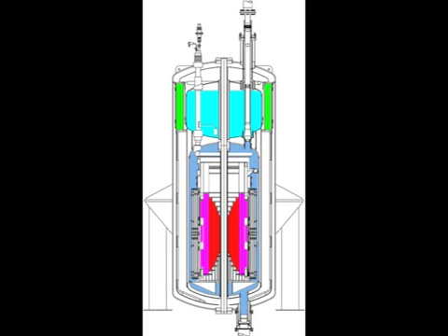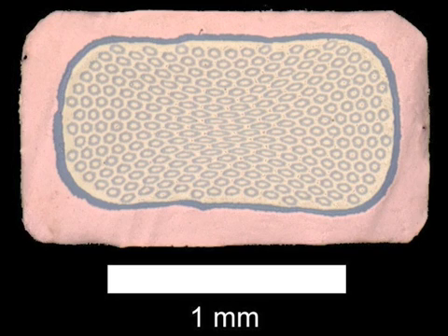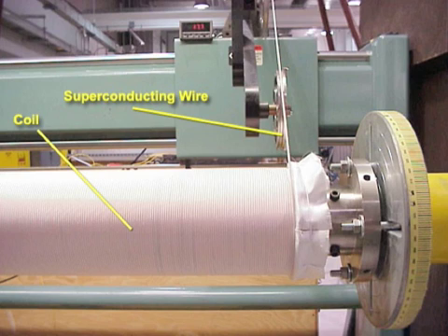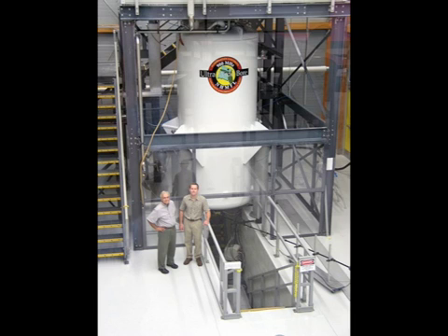The 900 was designed and built at the lab at a cost of 16 million dollars. It's made from 153 kilometers — or 95 miles — of superconducting wire wound into seven inter-nesting coils. Fashioned from niobium tin and niobium titanium, these wires carry 300 amps of current, enough to power two or three homes. The current travels around in a spiral, generating a magnetic field in the center. The superconducting materials carry electricity without any resistance or friction, so it just keeps on going — no voltage necessary.